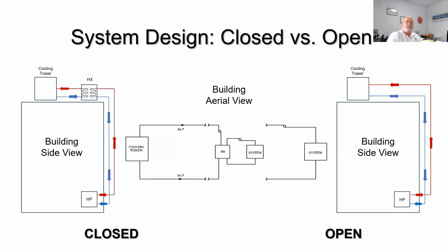We can take that heat exchanger apart and clean it, because another name for a cooling tower is an air filter — all the dirt and debris in the air gets sucked in and drops into that system. In the design process we'll talk more about filtration systems and basin sweeps, which depending on where you are may be necessary — something to discuss with your engineer.